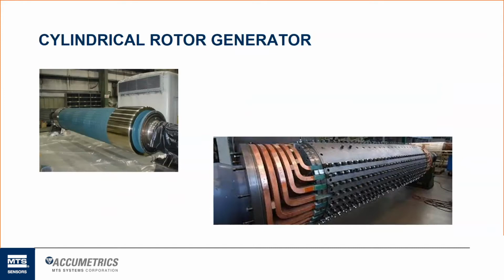and you can cause significant damage. The worst being with enough current flow, you can actually superheat this rotor to a point where it'll warp and bow, causing, as you would know, catastrophic vibration issues and cavitation and severe damage. And at that point would probably lead to replacing the entire rotor.